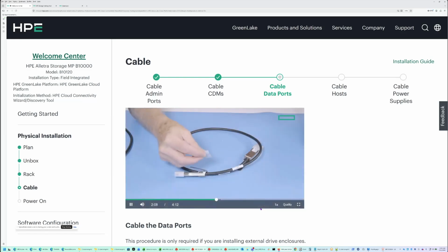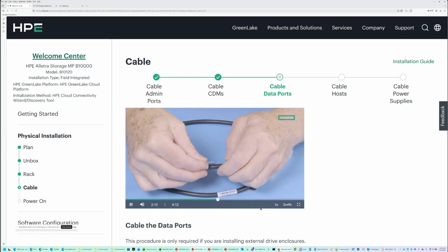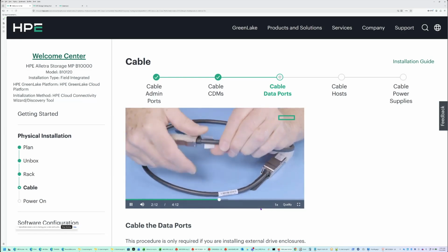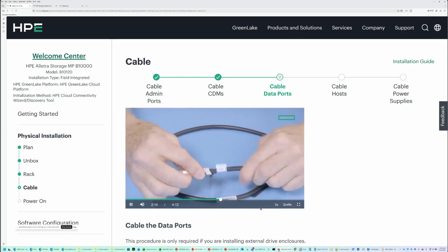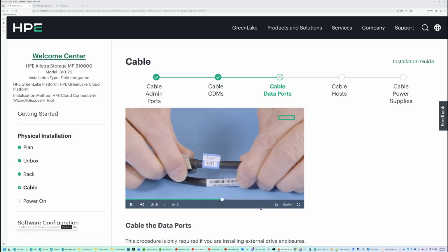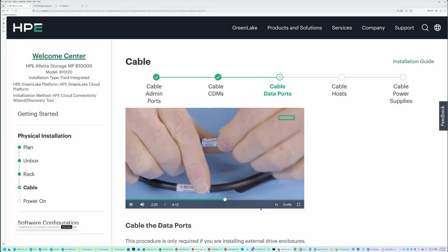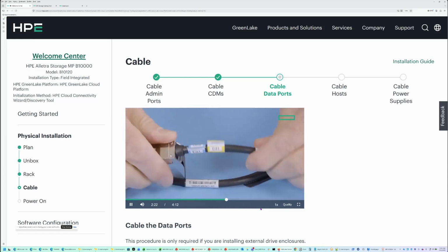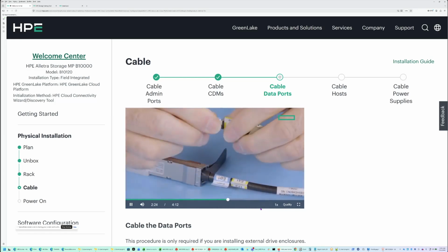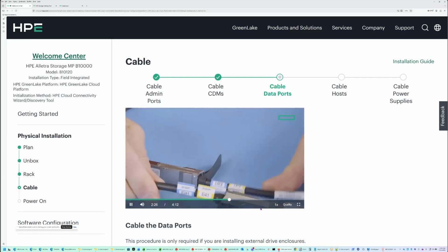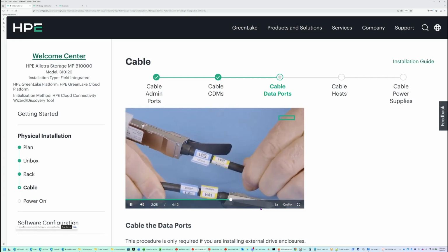The tool takes you step by step through the choosing of the appropriate cables, labeling, and connecting. For all cables other than the short half-meter internode cables, attach 2 labels to each end, including source and destination, with the destination always closest to the end of the cable.